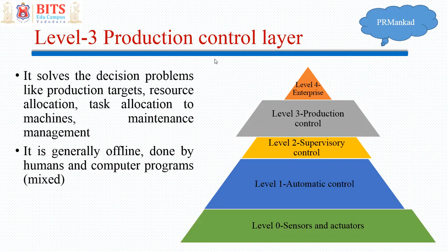And the top level is called the enterprise control level. This deals mostly with the commercial activities: what is the sales requirement, what are the orders, and based on that, how you are supposed to manage. So it is basically the MIS level and top level, and it is generally offline, done by humans, managers at the top level. But all the information from levels 0, 1, 2, 3 helps in getting to level 4. So level 4 is the commercial level management. Based on that, production control is done. Based on that, supervisory control is done. And then, whatever set points are there, as per that, automatic controls act, and sensors and actuators perform based on the set point and automatic control information which we have, right?